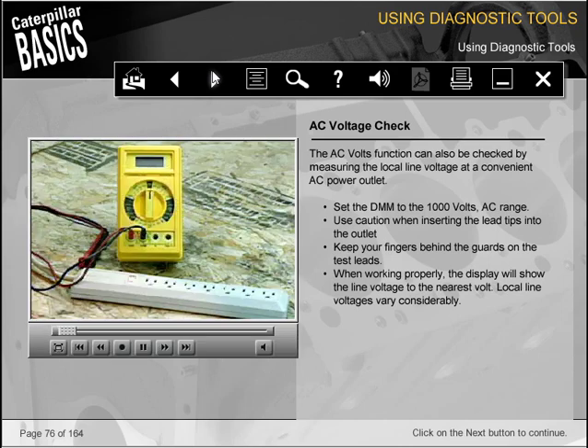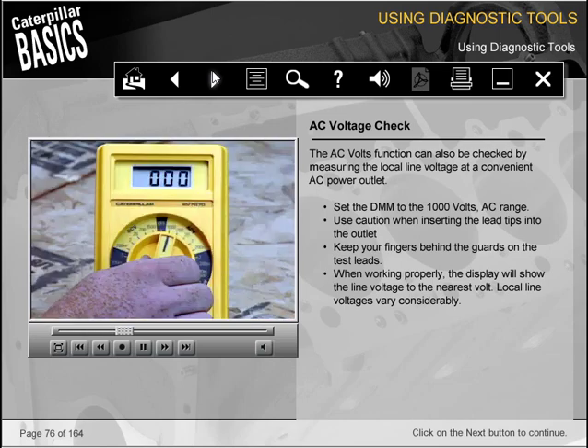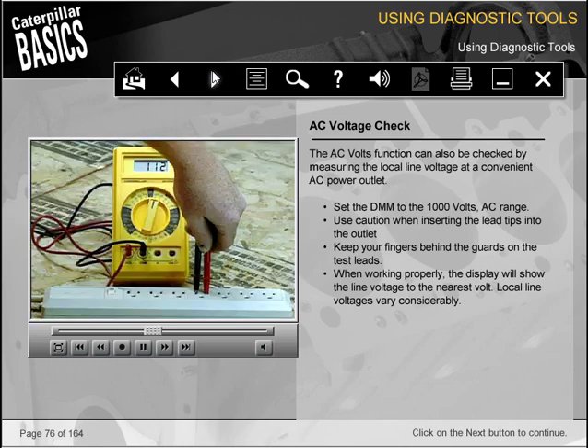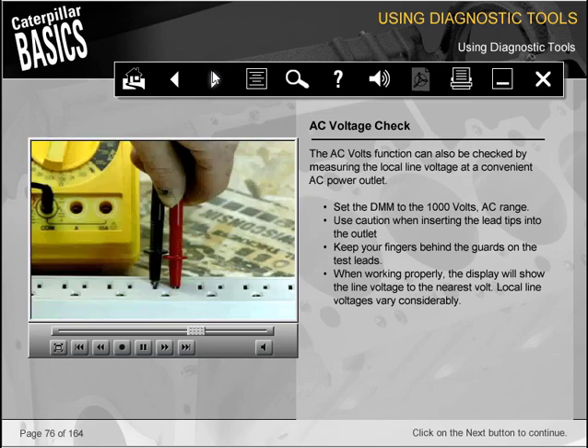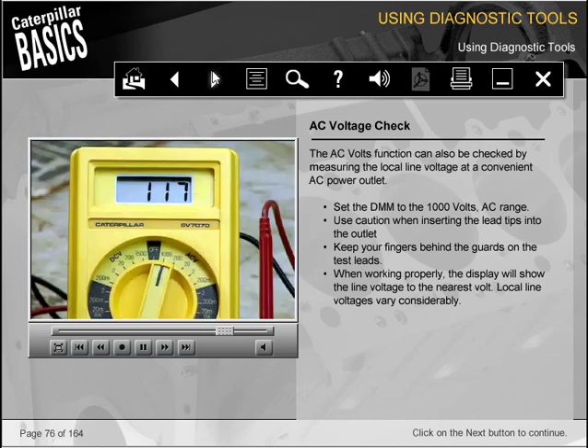The AC volts function can also be checked by measuring the local line voltage at a convenient AC power outlet. Set the digital multimeter to the 1000 volts AC range. Use caution when inserting the lead tips into the outlet. Keep your fingers behind the guards on the test leads. When working properly, the display will show the line voltage to the nearest volt. Local line voltages vary considerably.